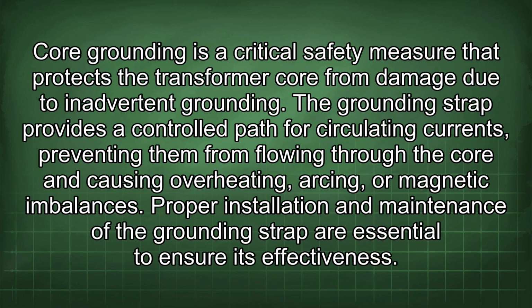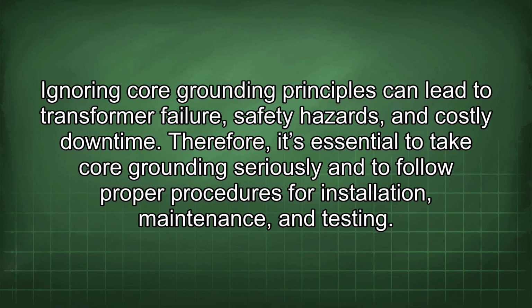Core grounding is a critical safety measure that protects the transformer core from damage due to inadvertent grounding. The grounding strap provides a controlled path for circulating currents, preventing them from flowing through the core and causing overheating, arcing, or magnetic imbalances. Proper installation and maintenance of the grounding strap are essential to ensure its effectiveness. Ignoring core grounding principles can lead to transformer failure, safety hazards, and costly downtime. Therefore, it's essential to take core grounding seriously and to follow proper procedures for installation, maintenance, and testing.